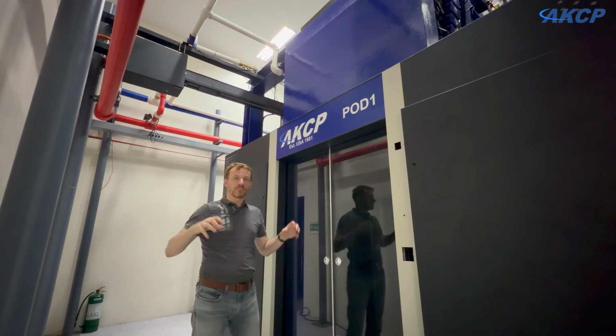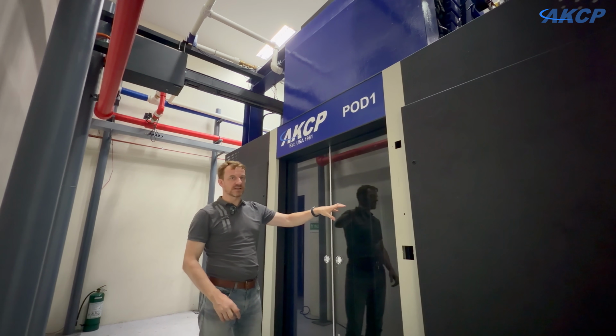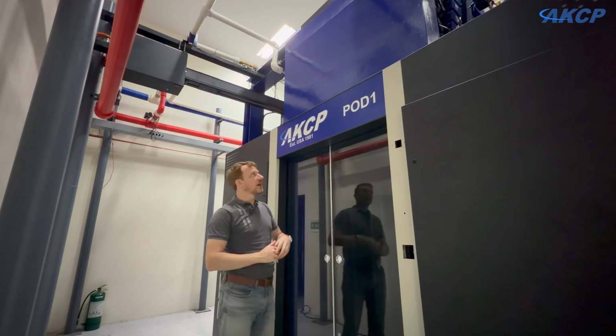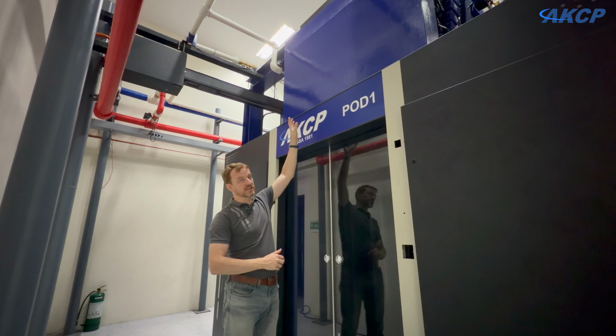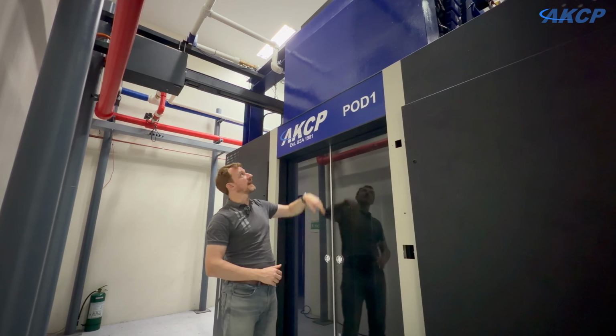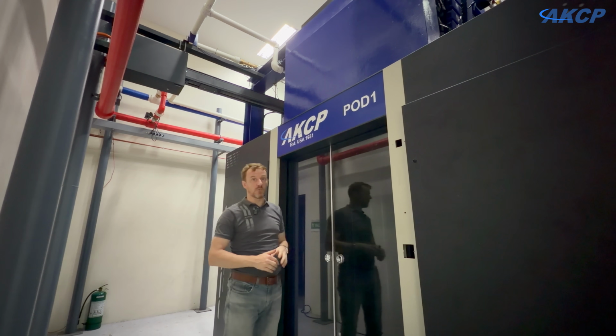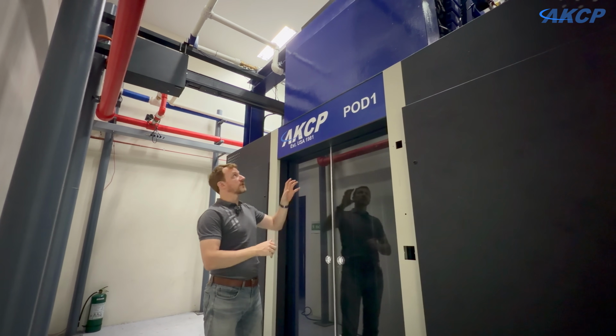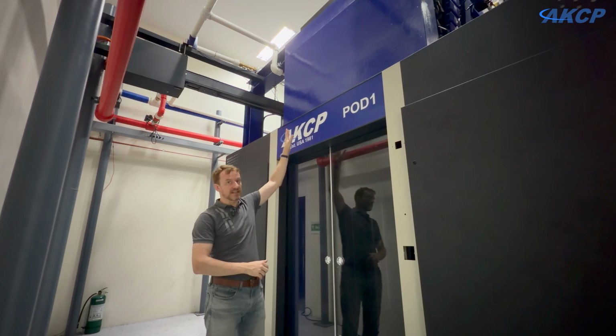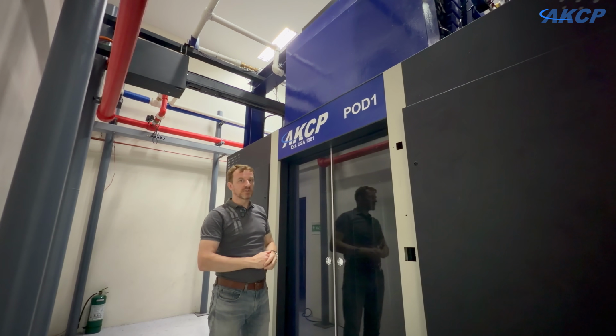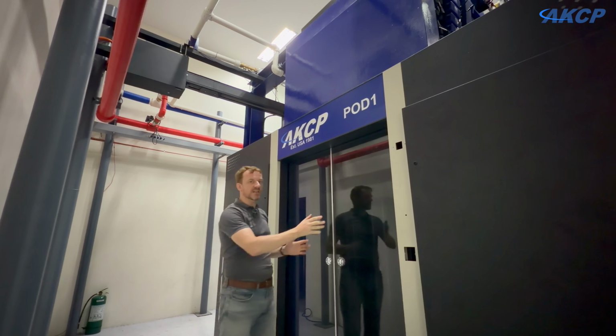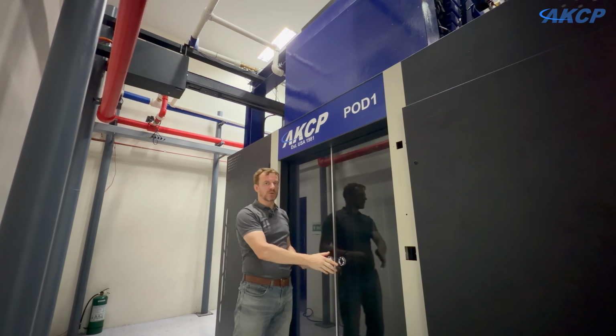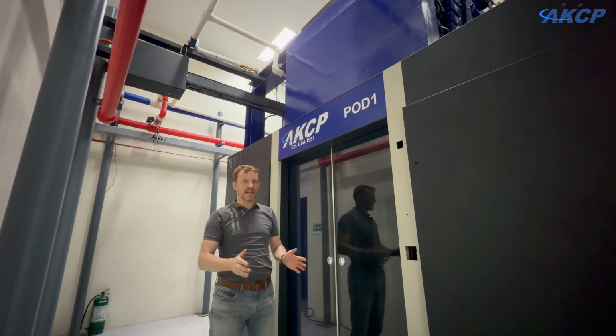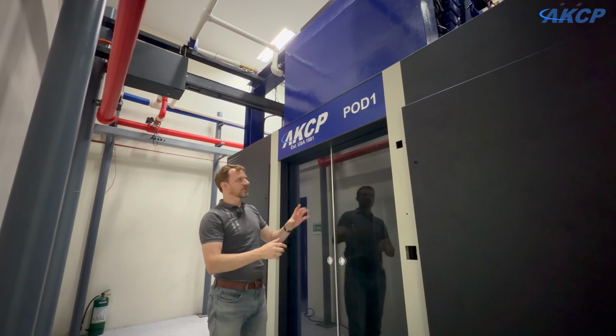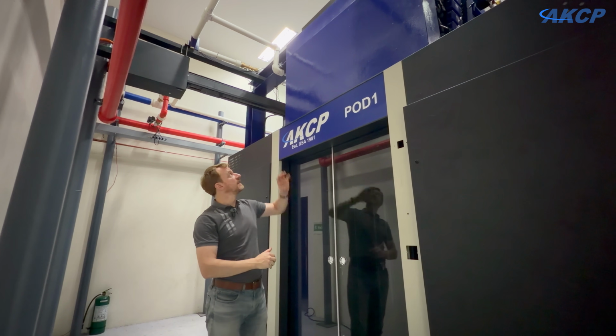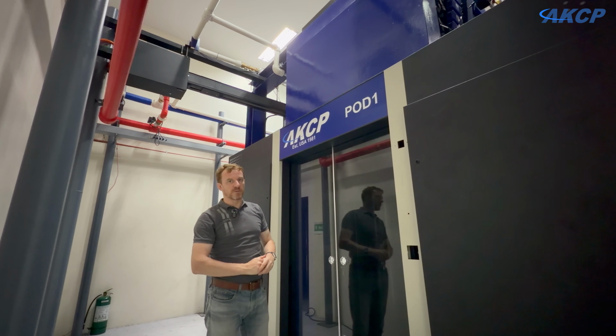In addition, in this pod, to the in-row air handling units, we've also got some unique overhead heat exchangers. So we can pre-cool the air as it comes out of there before going back to the fan wall, or we can also completely cool the air as it comes out of there by sending chilled water to the overhead heat exchangers. That frees up some space. You're not utilizing floor space then for the cooling units and the AHUs. Instead, you're able to put additional loads there with your racks, and we've shifted the cooling to above the pod.